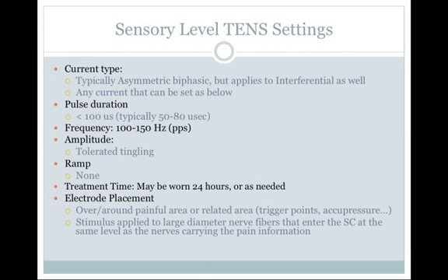You're going to ask your patients, do you feel this? And then take it up to a comfortable level of stimulation. There's no ramp, because really we're ramping this as we turn it up. So you're slowly turning it up, and then it's just going to run continuously. The treatment time can be worn as needed. So it can be worn continuously, worn for 24 hours. It can be turned on and off, basically, as your patient needs it.